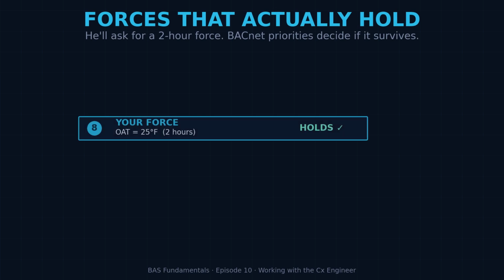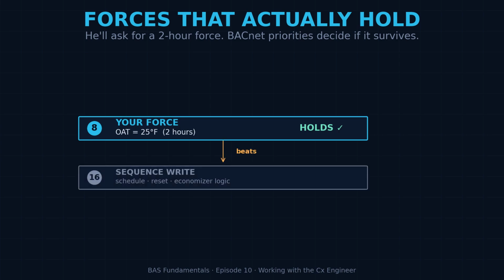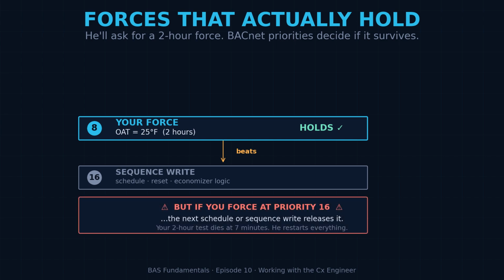Now, some things the Cx engineer doesn't know that you do. He is going to ask you to force things that the hardware can't hold. Force outside air temp to 25 for an hour. You can do that on most BAS, but if your BACnet priorities aren't set right, the force will release the first time anyone writes to that point through a schedule or a sequence override. Tell him. Say, I'll force it at priority 8, and the sequence writes at 16, so it'll hold, but let me confirm before we start the 2-hour test.